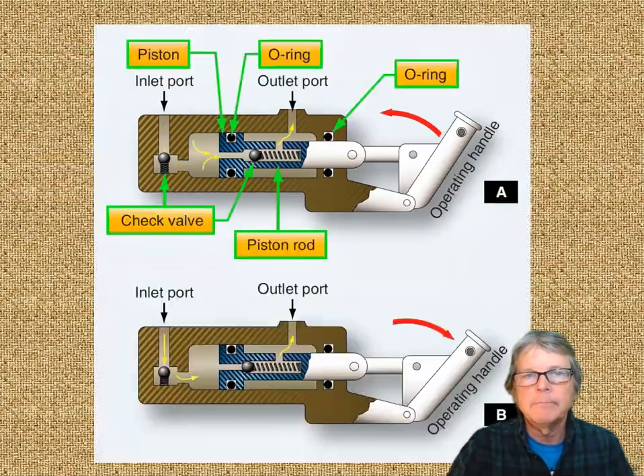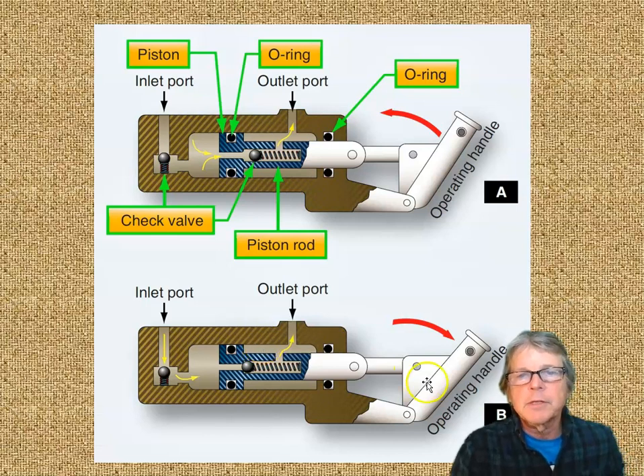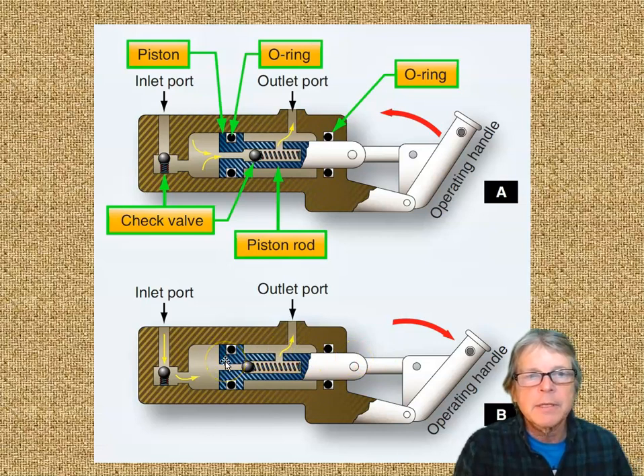If we put them all together, when we pull the handle towards us in B, it pulls the piston and opens this up. Like a syringe, it sucks the ball off and fills the reservoir. Then when we push forward in A, the chamber is full, and the piston moves back, the fluid seats the inlet ball and goes through the passage to the outlet. That's the hand pump.